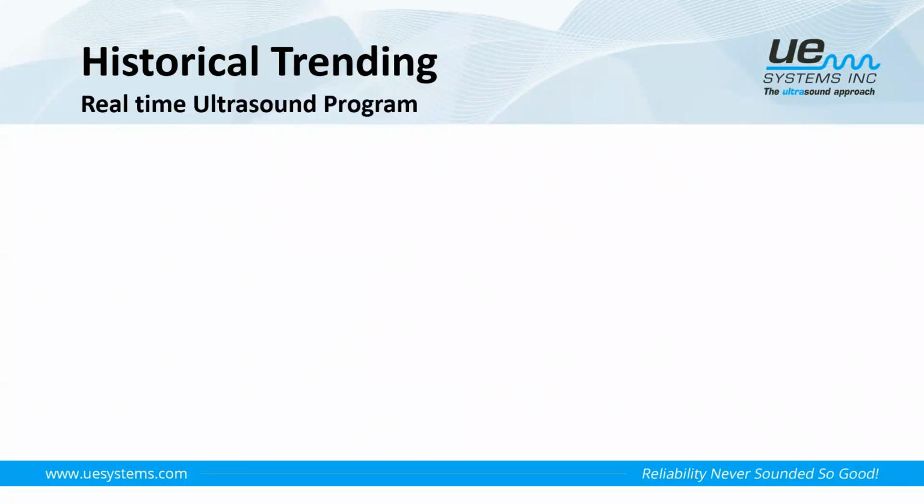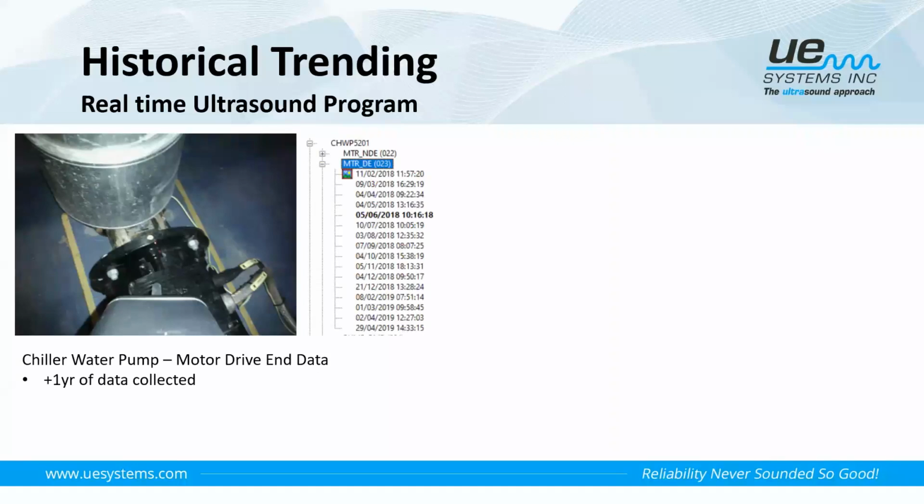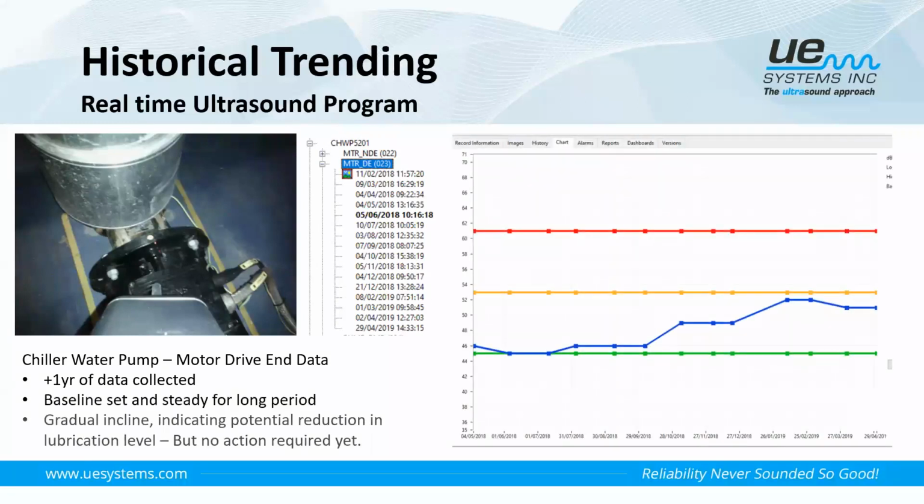So with historical trending, I want to share with you now some examples of a real-time historical trending ultrasound program from a user that uses this technology. One of these here is a chiller water pump, looking at a motor drive end bearing. We can see from the data here, we have over 1 year's worth of data points collected. We can see from the historical chart that the baseline was set and was steady for a long period of time. But then, over a shorter period of time, we start to see a steady climb in the decibel value. But we have not quite hit a low alarm level yet. So this shows to me that the bearing is getting closer to requiring some lubrication, because the level of lubrication is starting to reduce and the friction is starting to increase. So it gives us an indication that something's coming along here, and we might need to do something soon.